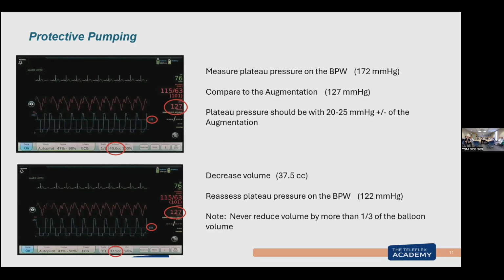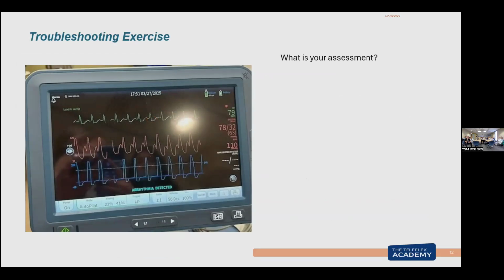calculation. Now I don't have to do that on every patient, but it's certainly helpful when I know I'm putting a lot of pressors on the patient. He's cold, he's clamped down. Maybe we were a little bit concerned about the size of the balloon for this position or for this patient, or if the patient's been restless, gets a hold of the catheter, corrects the sutures, pulls it down. The pump's still pumping, but this could be too high, and I could be getting those alarms.